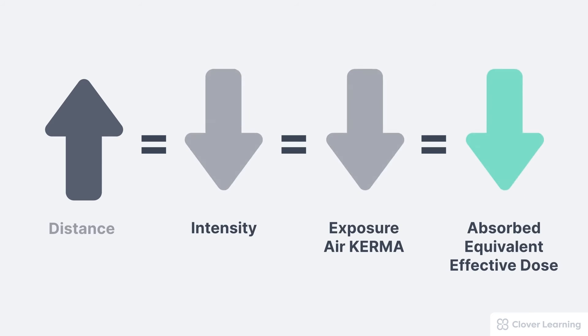We could also change the distance, and the result is different. If we increase the distance between the person and the x-ray source, this is going to result in a decrease in the intensity of the x-ray beam, which, according to the inverse square law, will then result in a measurable decrease in the exposure and air kerma. And if those things are decreasing, the absorbed dose, the equivalent dose, and the effective dose also all decrease.